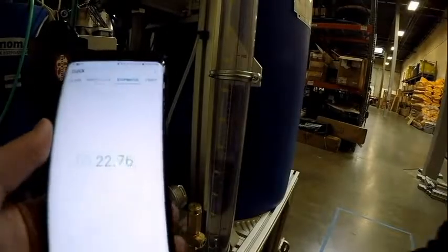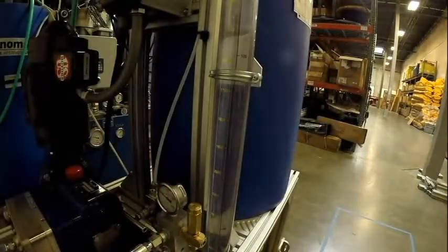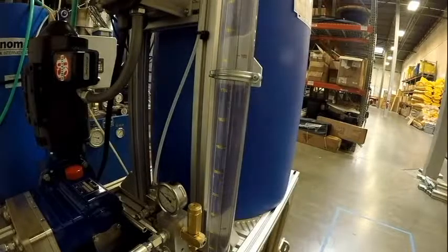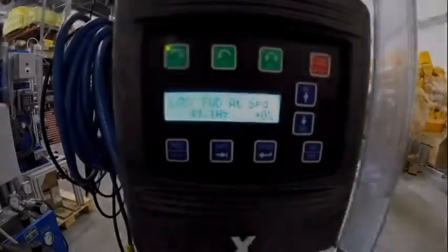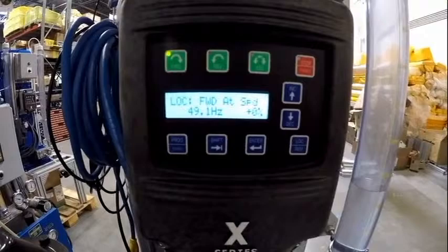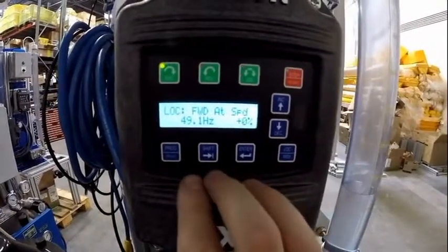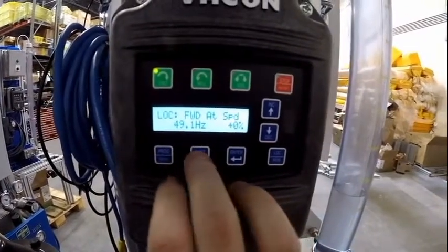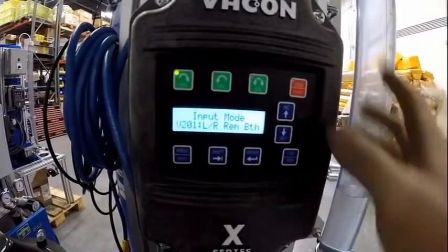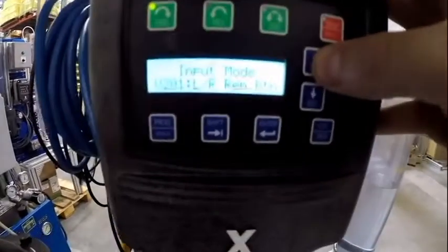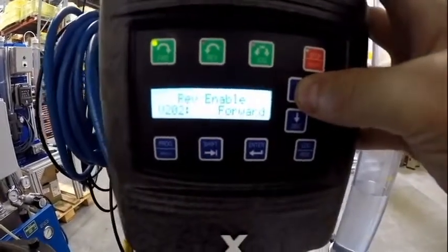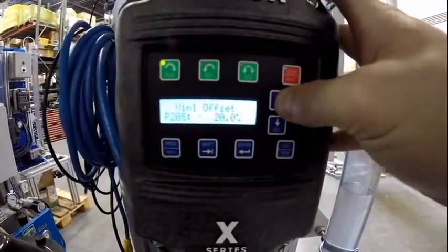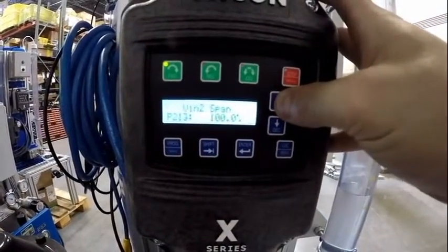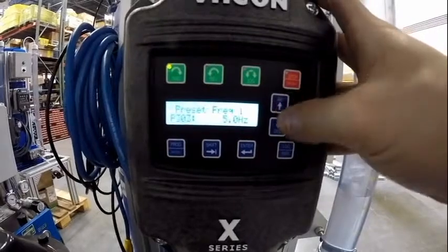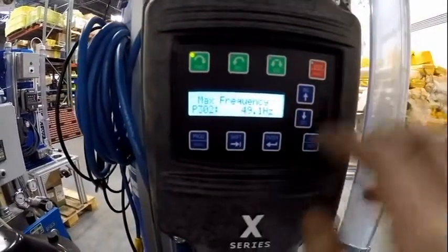As you can see here, it's dropping fairly quickly. So what we're going to do is stop it, bring it back to the top, and move over to the Vacon VFD. To get into the setup window, you need to hold shift and push the program button. Then use the arrows to move up and down. We're looking for parameter 302, which is max frequency.